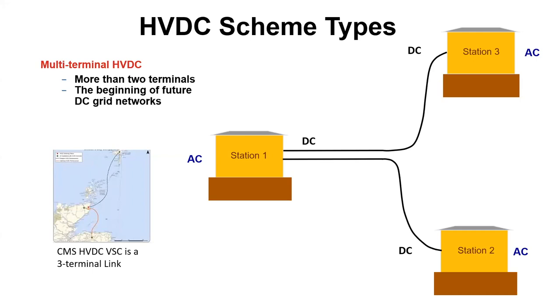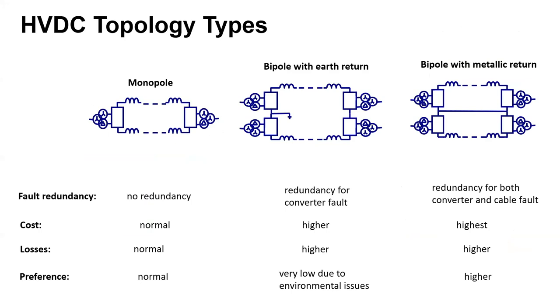All these configurations can be arranged in different topologies, or electrical circuit connections. These topologies are monopole, bipole with earth return, and bipole with metallic return. The difference between bipole with earth return and with metallic return is that the one with earth return uses ground or sea electrodes, not a cable or overhead line, which is the case with bipole with metallic return, to carry the current when the redundancy is lost.